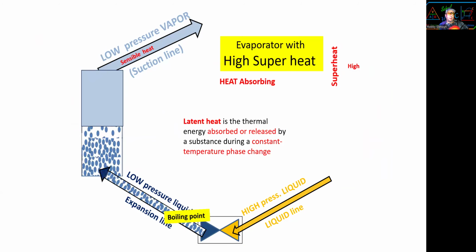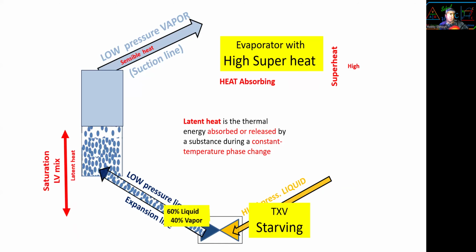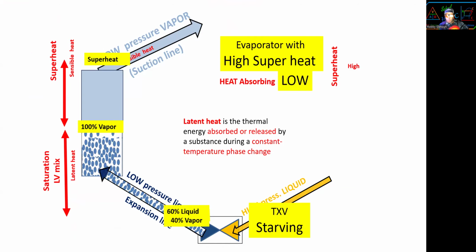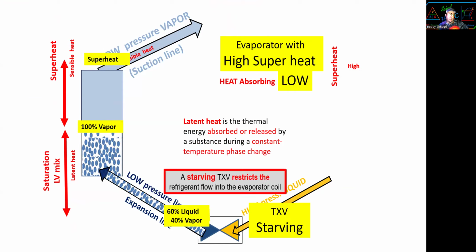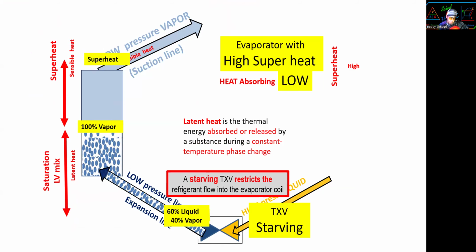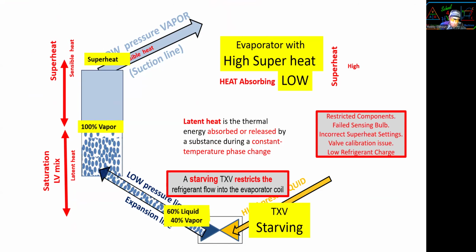Saturation temperature, the boiling point, minus the suction line temperature at the end of the evap equals superheat. All right, now, what happens with high superheat, a starving TXV? 60% liquid, 40% vapor. We have very little latent heat, 100% vapor towards the middle. We have very high superheat, heat absorption very low. A starving TXV will restrict the flow of freon into the evap coil, right? Because of a maybe failed sensing bulb, incorrect superheat setting, valve calibration, or low refrigerant charge.